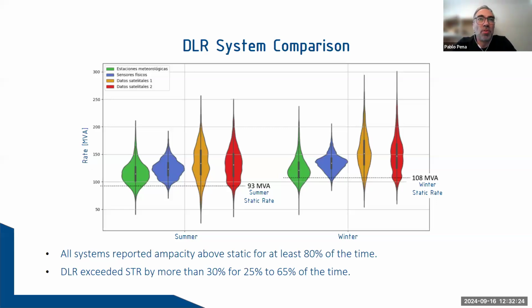Now, let's look at some results of this experience. This violin plot showed the performance of 4 different dynamic line rating systems over a full year, separated by winter and summer. In blue, we have the system based on a physical sensor attached to the conductor. The green represents a system using a weather station, while the orange and the red represent 2 sensorless systems. All systems reported ampacity above static for at least 80% of the time.